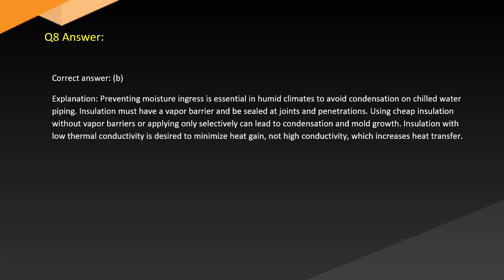Answer. Correct answer. B. Explanation. Preventing moisture ingress is essential in humid climates to avoid condensation on chilled water piping. Insulation must have a vapor barrier and be sealed at joints and penetrations. Using cheap insulation without vapor barriers or applying only selectively can lead to condensation and mold growth. Insulation with low thermal conductivity is desired to minimize heat gain, not high conductivity, which increases heat transfer.